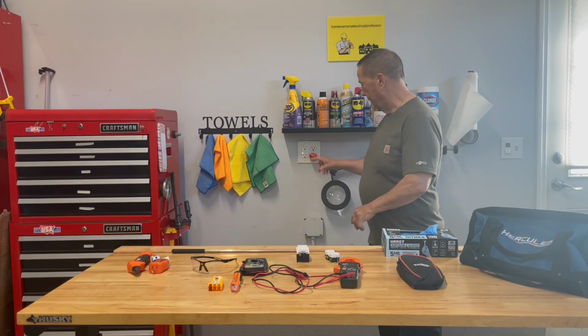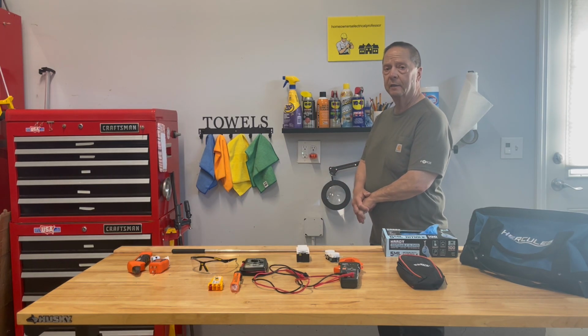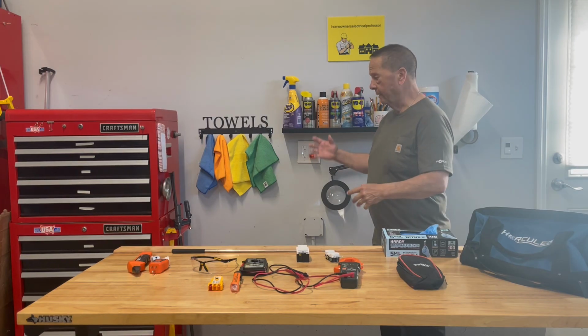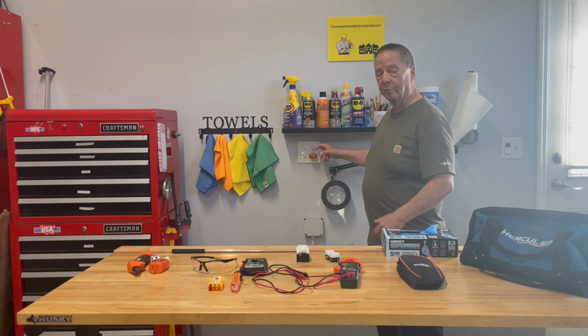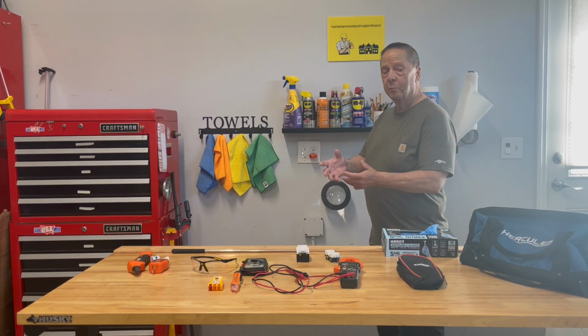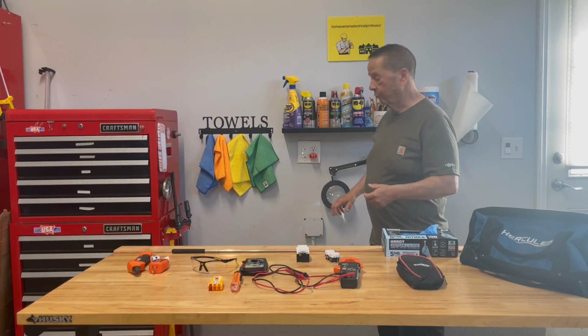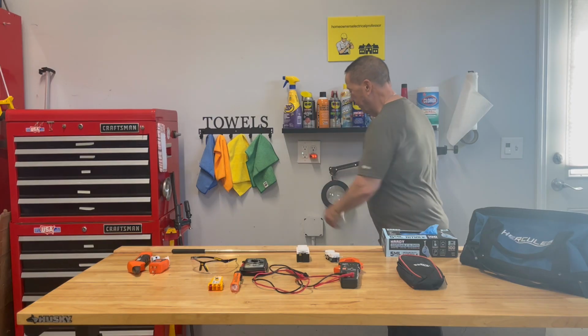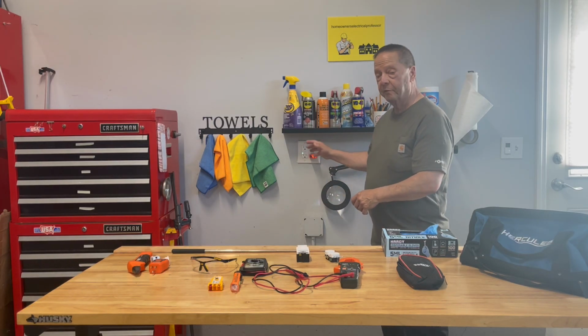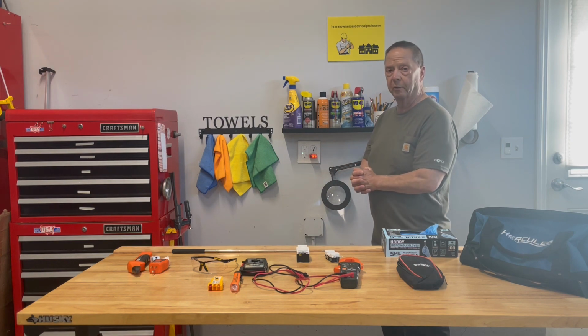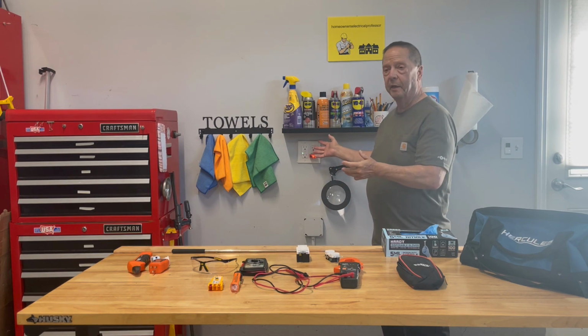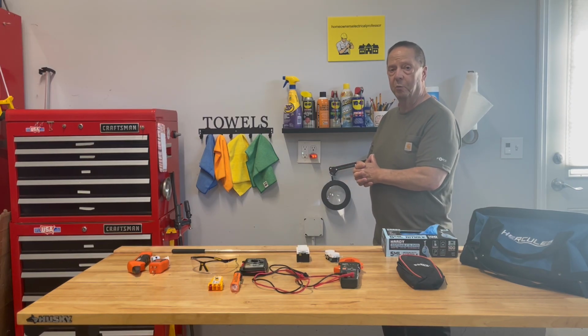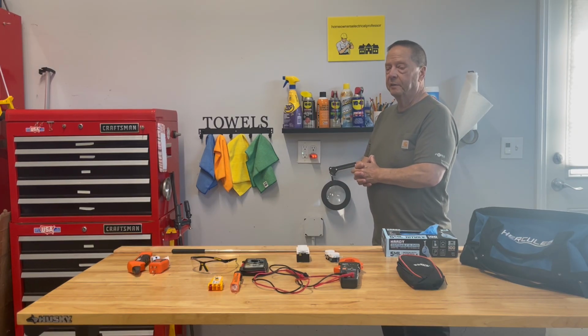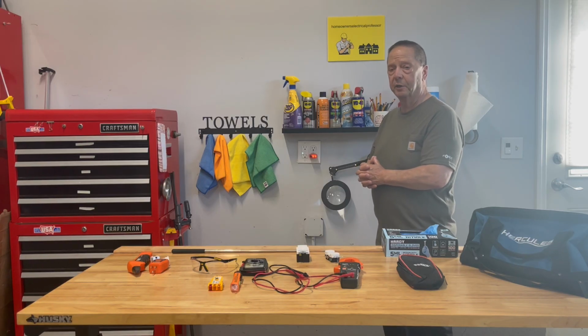You plug your tester in and you have no lights lit, it means your hot or ungrounded conductor is not providing electricity. Now in this case we have a receptacle that's fed downstream from a ground fault, much like your kitchen counters and your bathroom receptacles. It may be a simple thing of resetting the ground fault. The other thing could be, if you don't have any power here, of course, is the circuit breaker. And if those are both on, then again, you might have a problem in a box with a bad connection somewhere, especially a wire nut connection if your house is old. If your house was wired in the 50s and 60s, you know, those connections have been there for quite a while. So, very useful tool if you're having problems with receptacles.